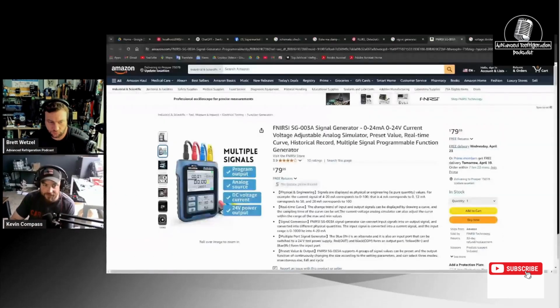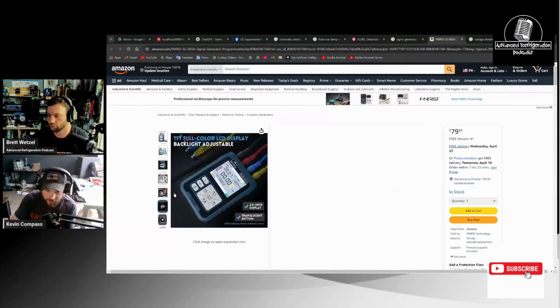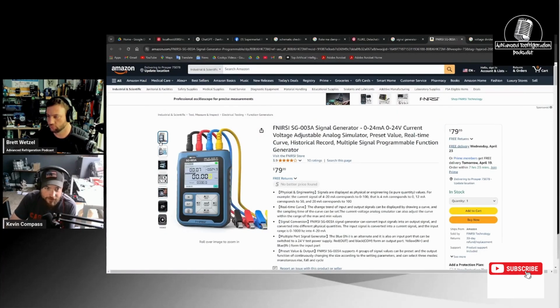Because if you flip the transformer feeds, say for an IDCM, this is super common in the protocols. Somebody will change a board and they'll flip around the hot and the common on the IDCM. Super easy to do. It's a yellow and a blue wire. When you do that, you put 24 volts AC on the common of the signal input. So what ends up happening is it smokes the board point on the AO board for Copeland or Danfoss or Micro Thermo, whoever it is, because that common should have 0 volts on it. Now it has 24 volts and the hot has 10 volts or 5 volts. There's a voltage difference, so it smokes the input.